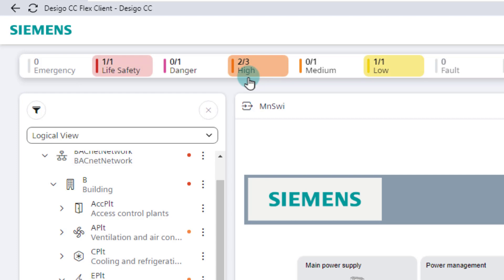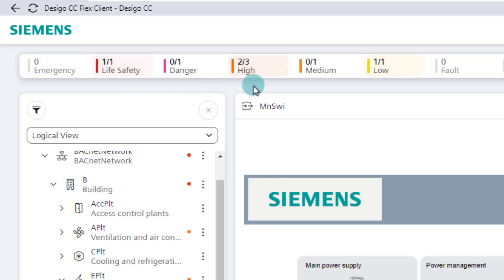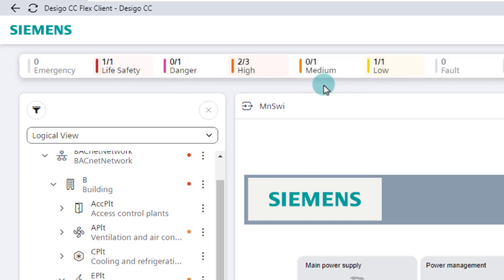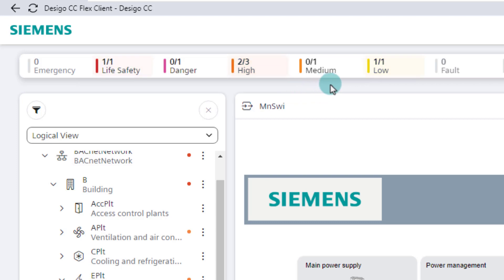An event lamp flashes in the color of the event if there are events in this category that have not yet been processed, as can be seen in our example for the life safety, high and low categories, and also when new events occur in the system for this category. A solid white background means that there are no unprocessed events for that category, visible here with the categories danger and medium. An event counter at 0 and white background means no events for this category.